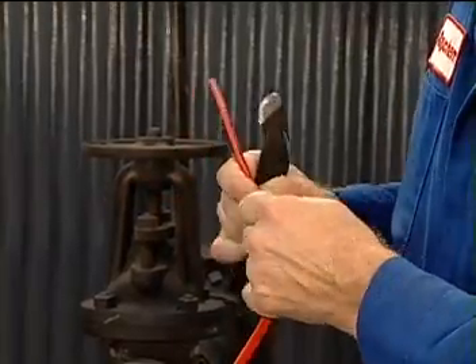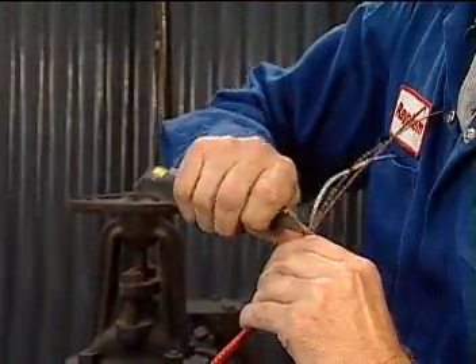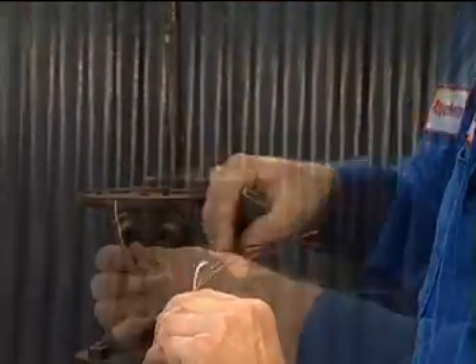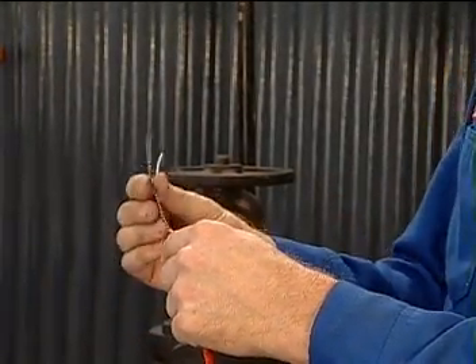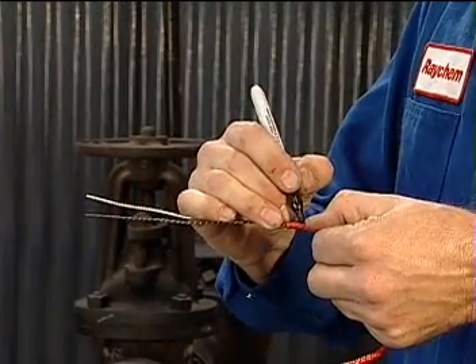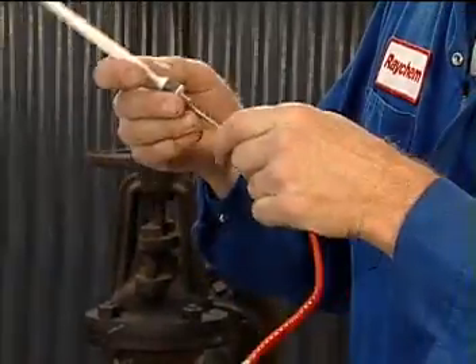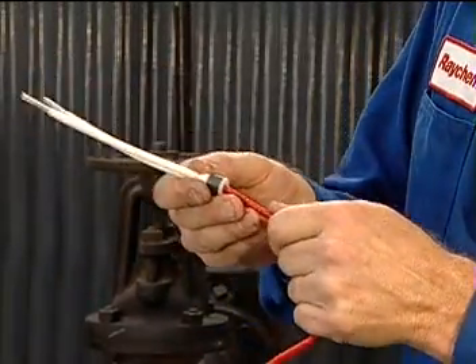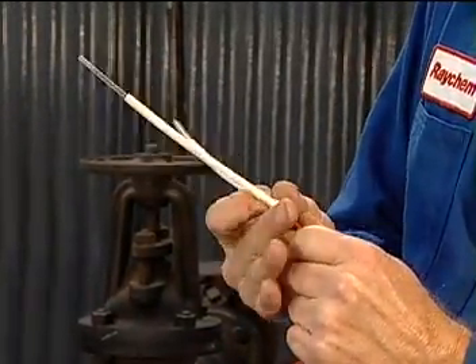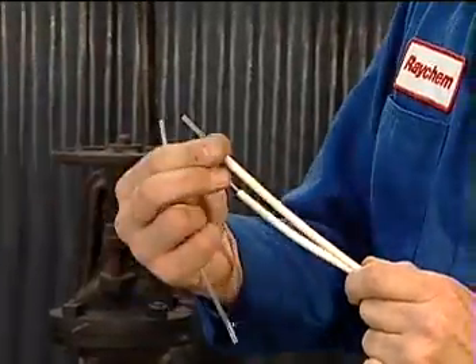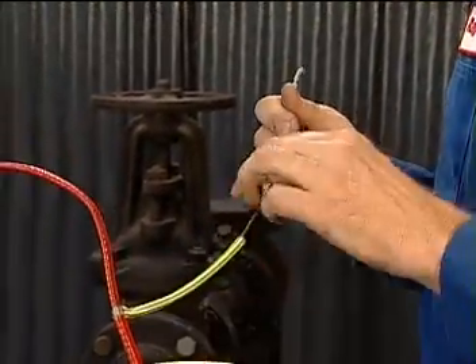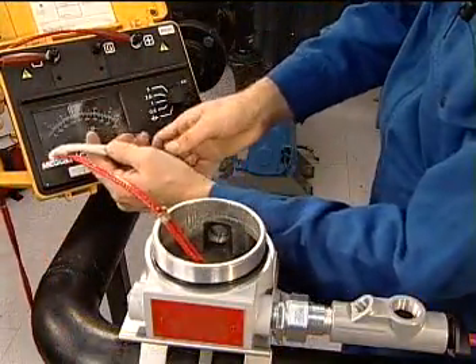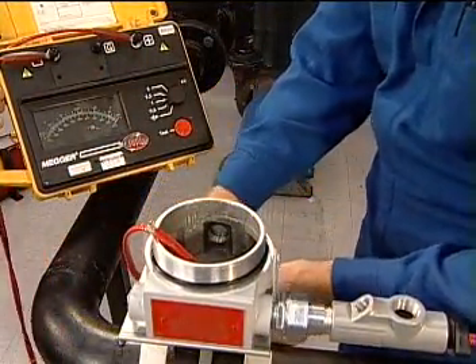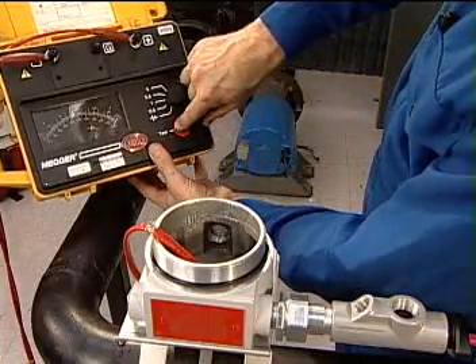Strip off 6.5 inches of the inner jacket. Remove the conductive core or fibers of the heating cable in the same manner as for standard cables. Mark 5/8 inches on the inner jacket as a reference point. Insert the bus wires into the guide tubes, making sure to seat the core seal onto the cable. Slide the green and yellow tube over the braid, then trim the bus wires and the braid. Test the insulation resistance of the cable from bus wires to braid and braid to system ground.